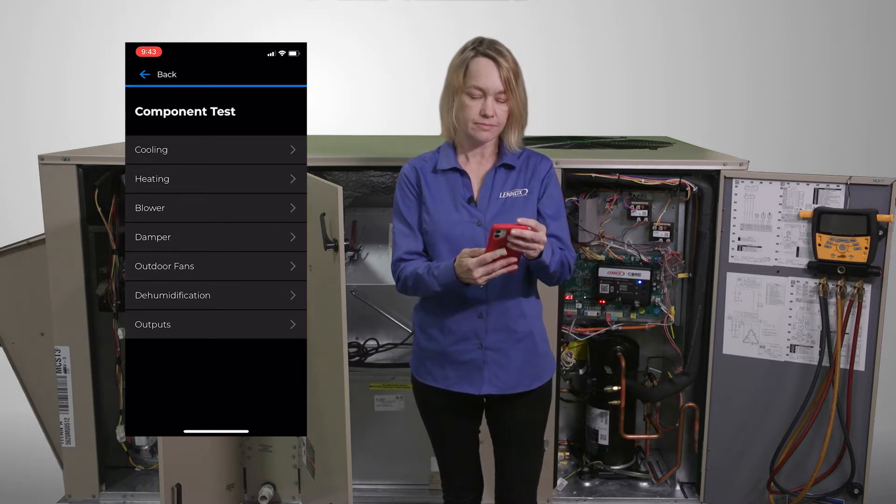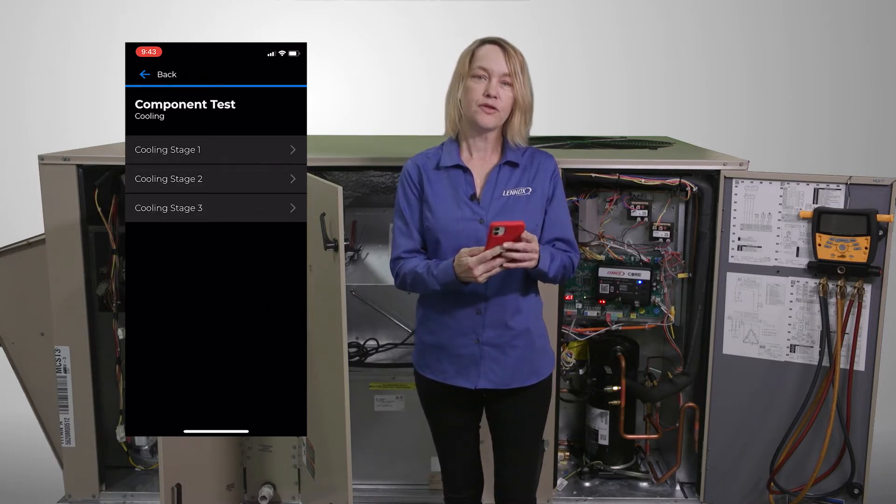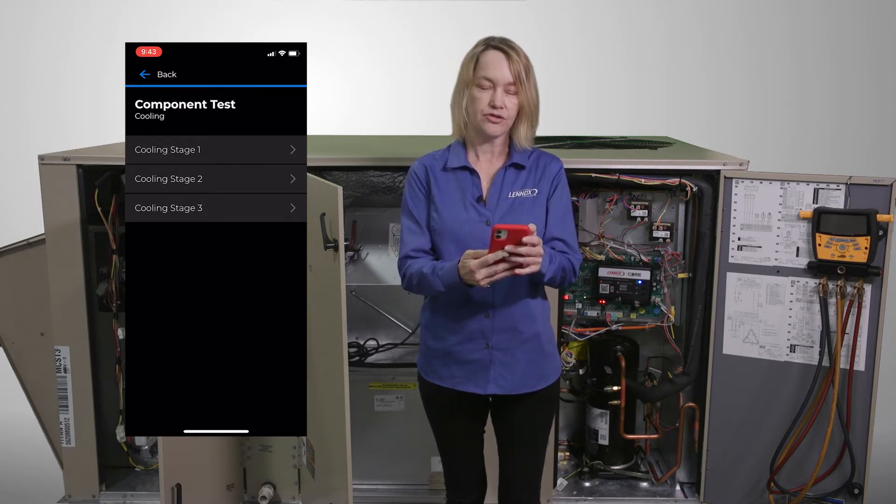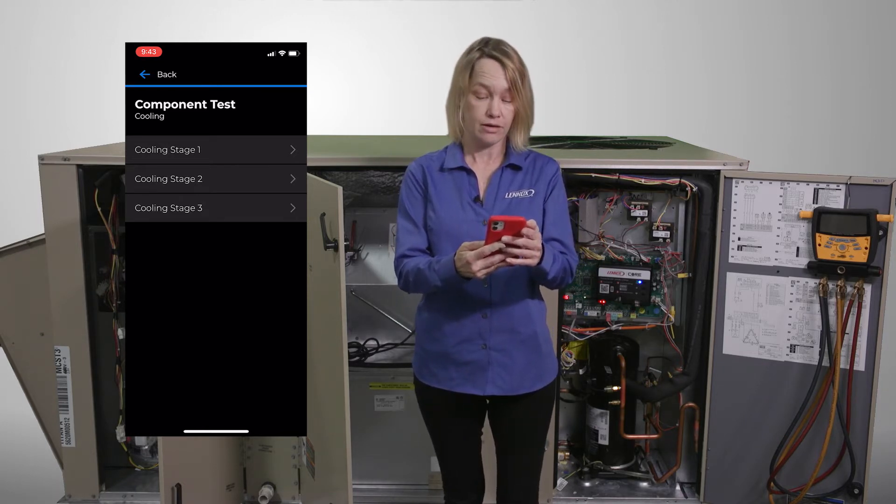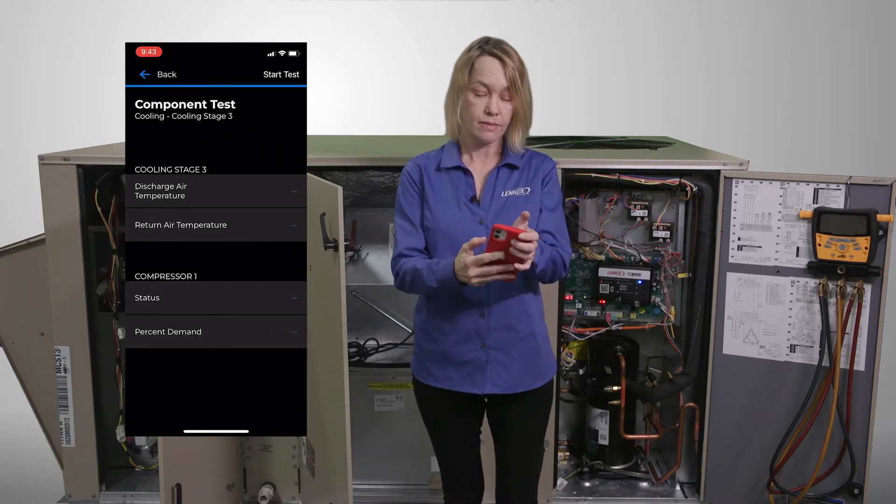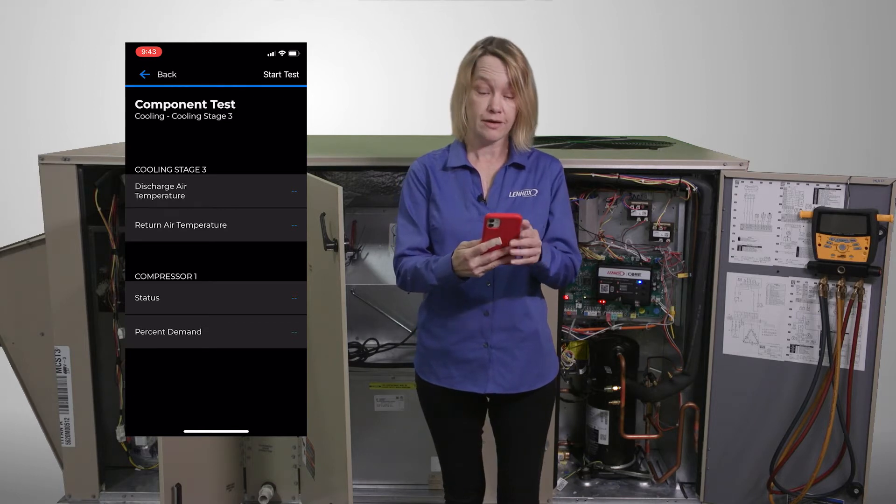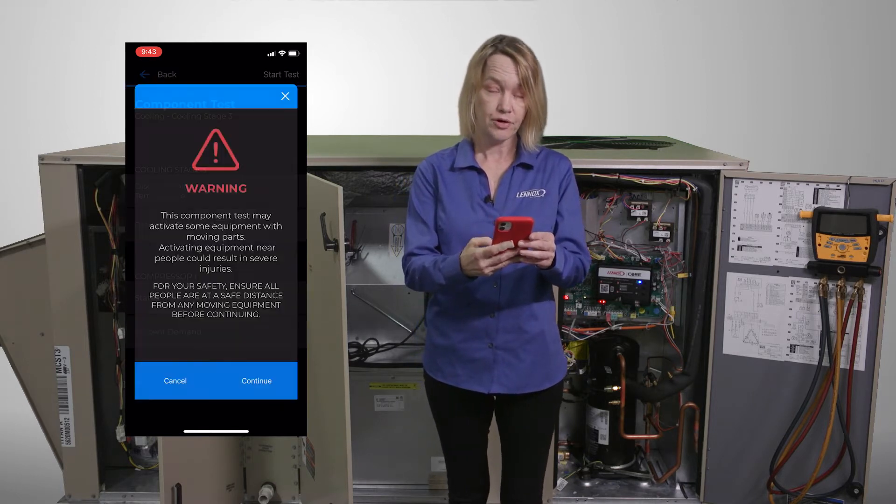Let's start with the cooling test. We want to make sure that the unit is in a full call for cooling, so we'll select the highest cooling that we can. We enter the test menu, press start test. Make sure no one's in the way of the blower. Press start.